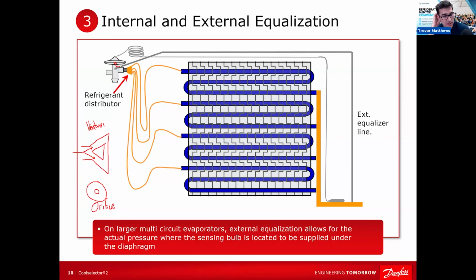What's your experience on that, Jamie? To be honest with you, I can't single it out. I've seen them where they have mounted the external equalization line on the bottom. It's almost like they're trying to drain oil from the system. Oh, fill it up with oil. I've seen that before. And generally what ends up happening is the TXVs are unresponsive. And I can't remember now if it was open or closed. Yeah. All I remember was I could never find the person responsible for doing it.